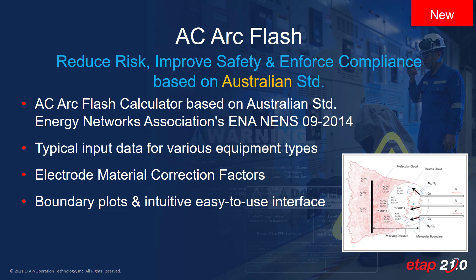The Sweeting method remains a very reasonable method still in use in several countries and utilities in Australia and around the world. This method has been implemented in ETAP21 in the form of a calculator, which has user-friendly typical input parameters, includes considerations for the thermal energy and melting properties of different conductors like copper and aluminum, and also provides several plots and an easy-to-use intuitive interface, which makes what-if scenarios very easy to execute.